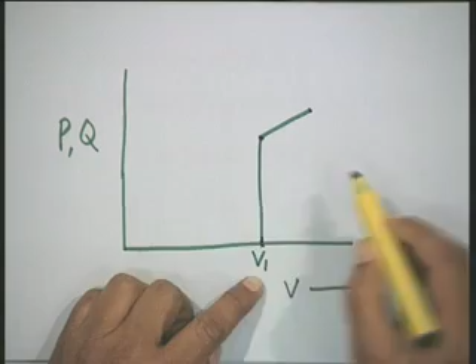In fact, you can take this nonlinear characteristic and represent it by a piecewise linearized model. From V1 to V2 it can be represented as some Kp1 into V, and in the next segment as Kp2 into V. So far as reactive power consumed is concerned, its variation is very non-linear in nature. This type of curve we can call Q, which is equal to Q naught, the value at this particular point, multiplied by V to the power of some coefficient K. A very non-linear type of variation. Since system voltages vary, when you want to model these devices, if the voltage is less than V1, they are off. When it is between V1 and V2, P and Q have to be shown by this. That is, in the model you have to have the facility to represent the loads as a function of voltage.